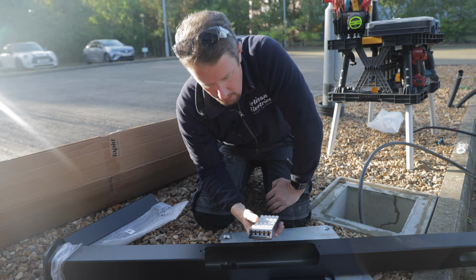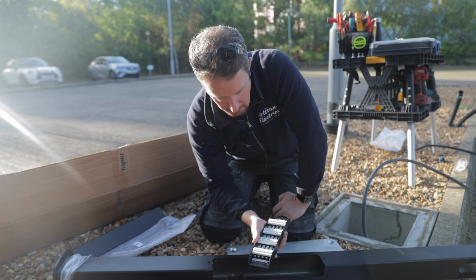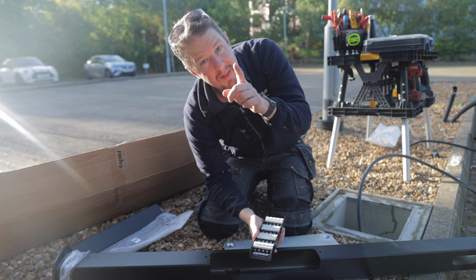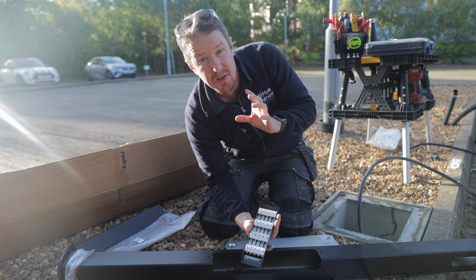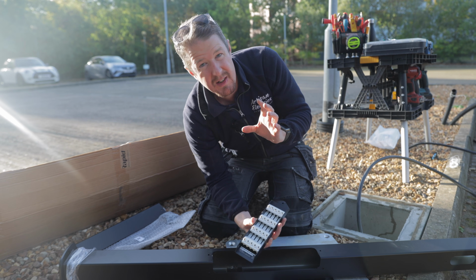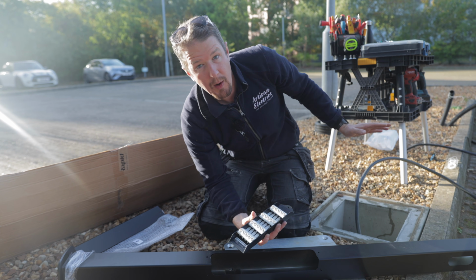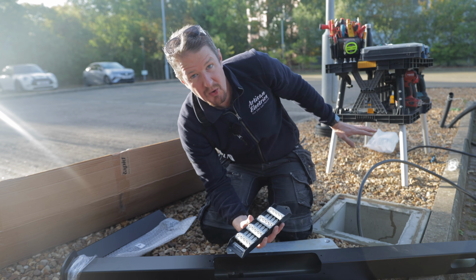You could run it on an 80 amp circuit, for example, and loop in and out of here between various pedestals, because with the Easee chargers you can have up to, I think, 100 charging points off one circuit, and they'll do load balancing between them all.